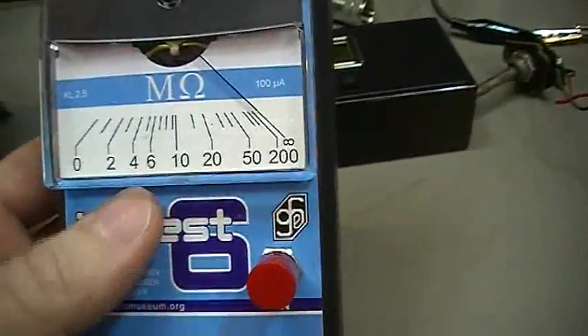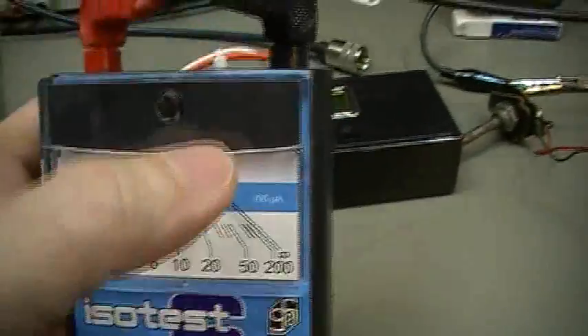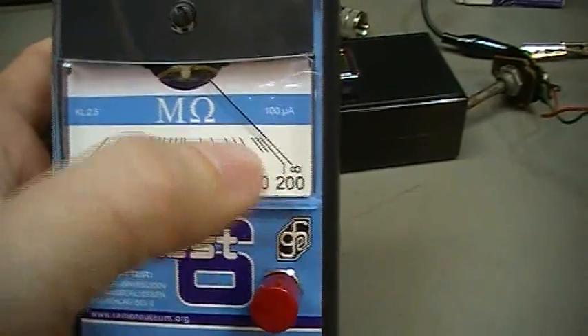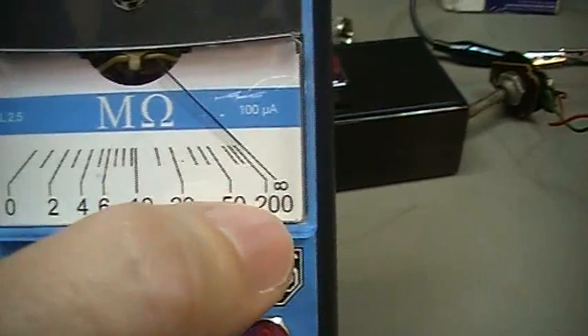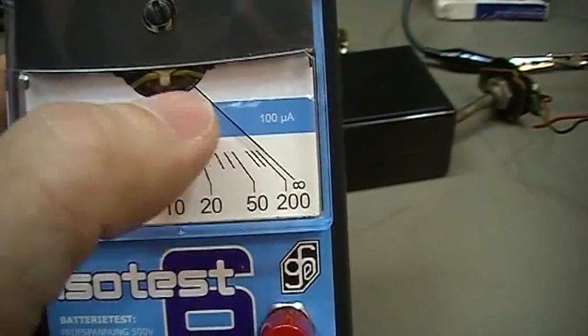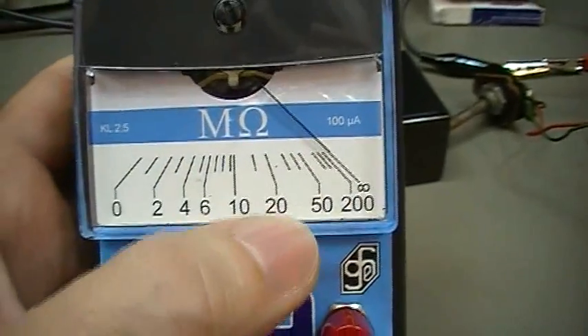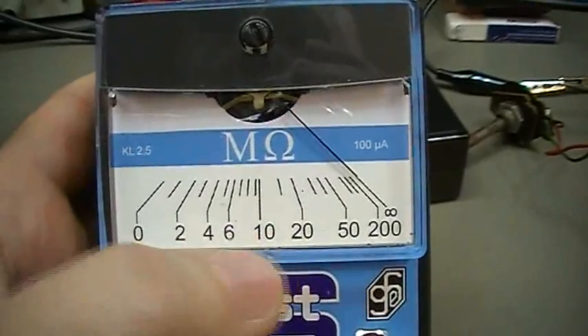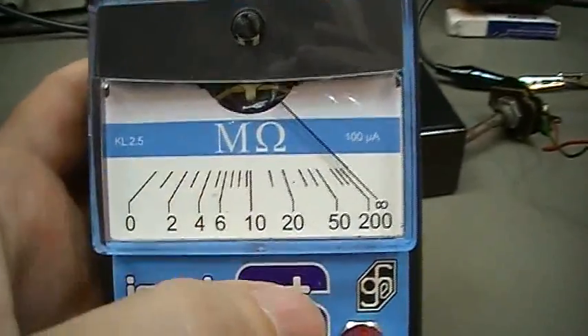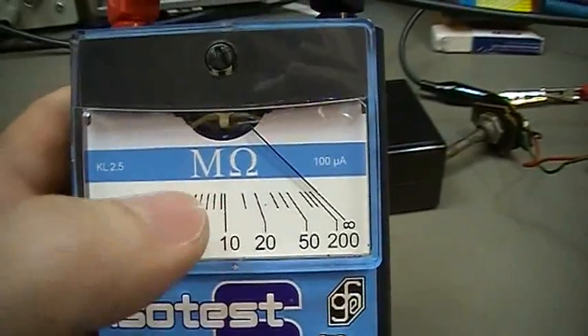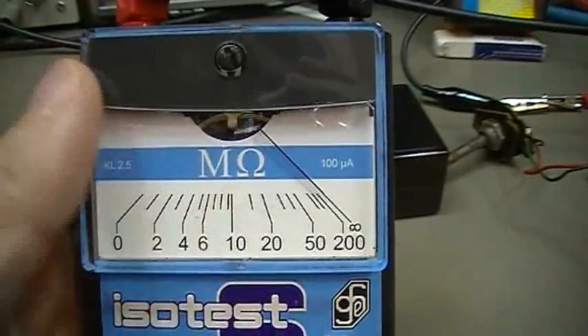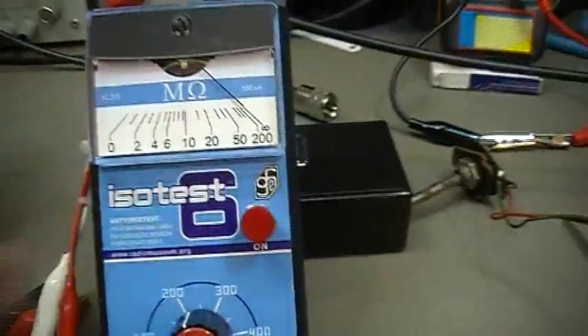Then I connect the leads to the capacitor and start measuring. What I want to see, in the best case, is that we don't have any movement of the needle, because that means the resistance is infinity. If the needle is moving, you can see 20 mega ohm, 10 mega ohm, 6, 4, 2 mega ohm. So that is a mega ohm meter for high voltages, a very, very handy device.